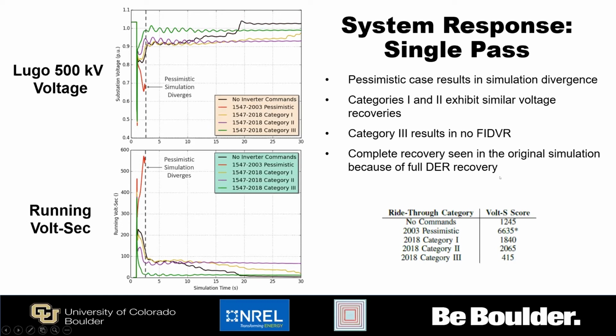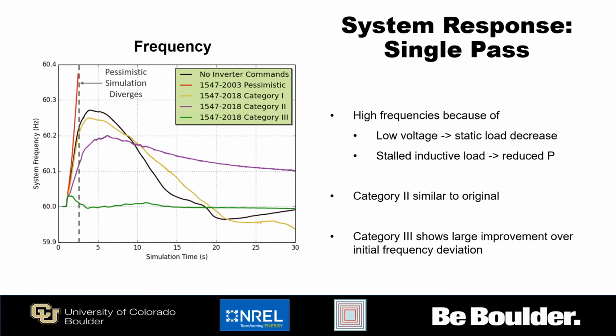We can also quantify this in terms of the volt-second score, which is basically the summed deviation of voltage over time, and you can see it is far less for category 3 than it is for categories 1 and 2. Looking at the system frequency, we also see the 2003 pessimistic case diverges here as well, whereas we have frequency recovery much closer to 60 hertz for the category 3 case than for the category 1 and 2 cases. Now, you may be asking, you had this fault on the system, so why is the frequency going up instead of going down?